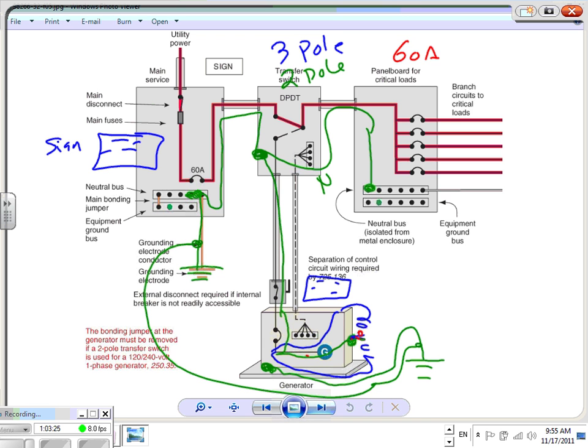Sign number two, that you guys have to have right next to here. This is brand new in 2011. Look at this sign. Phil, my friend, what happens if I tamper with the grounding electrode conductor while the generator is running? What happens if I tamper with the grounding electrode conductor if it's a non-separately derived system? What happens if I unplug this bonding jumper, or the grounding electrode conductor, meaning disconnect it because I want to service it?